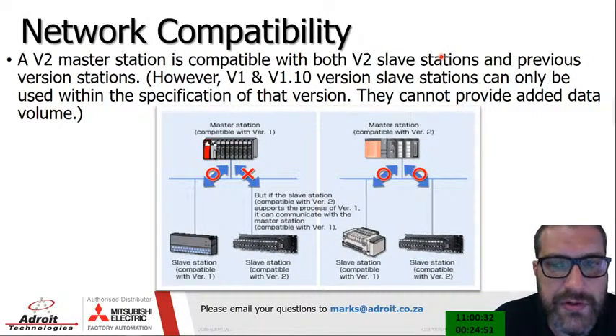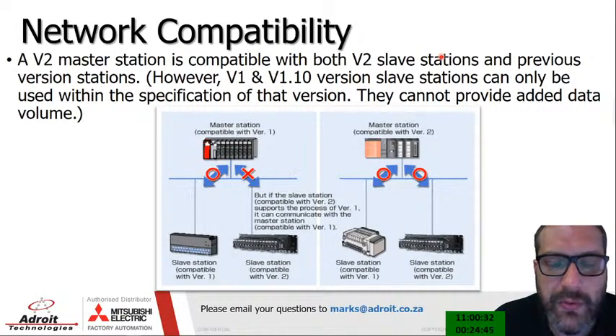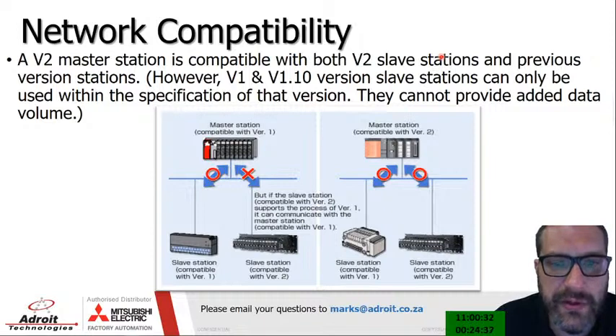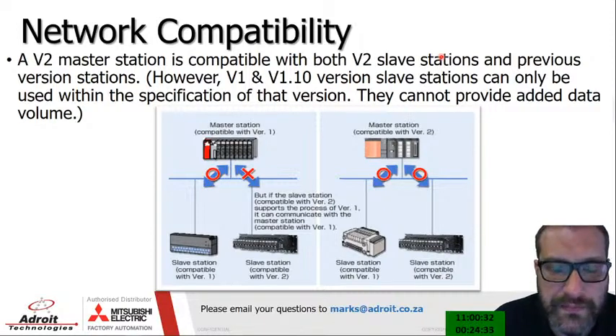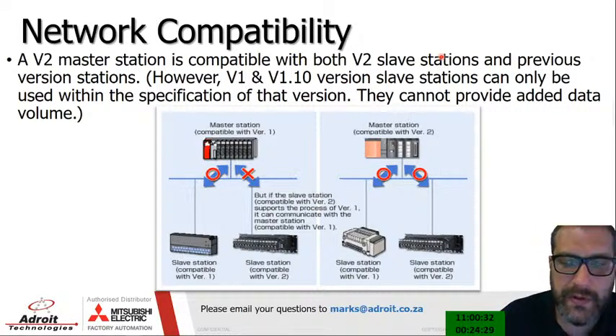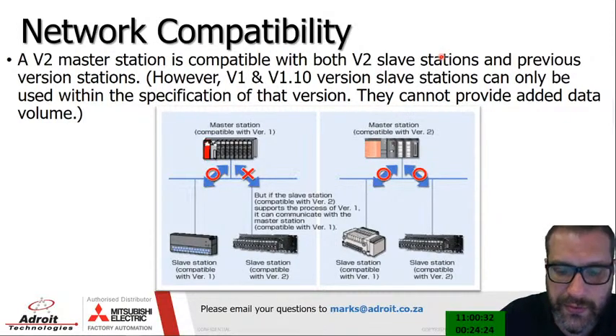Regarding network compatibility: a version 2 master station is compatible with both version 2 slave stations and previous version stations (version 1 and version 1.1). However, slave stations can only be used within the specification of their version — version 1 slaves cannot provide the added data volume of version 2.